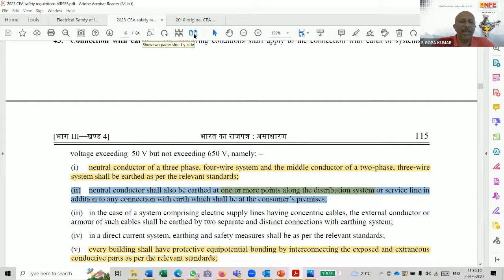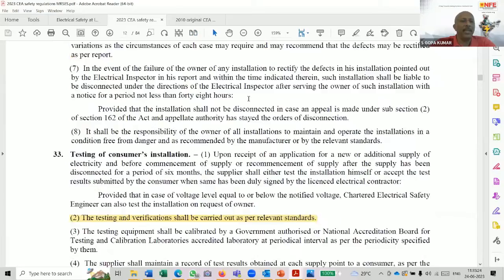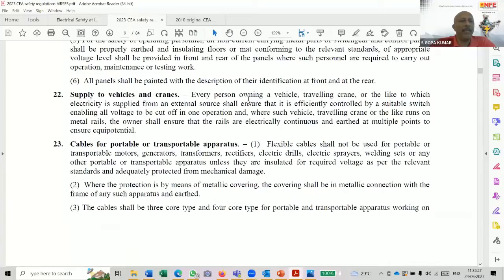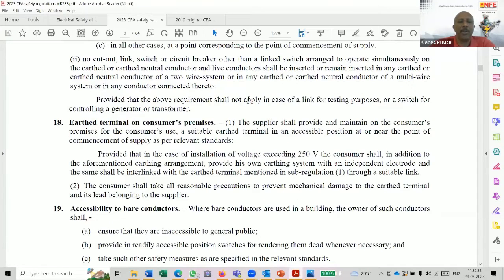So, sir, to conclude, in the majority of cases, the earth terminal under regulations 16, 17, 18 of the current regulations, especially the earth terminal in regulation 18, which was earlier regulation number 16, was not provided by the electricity supplier. Actually, I was in Kerala last week. There, the electricity supply company is giving a funny network. It looks like a TT, but on the distribution, the neutral conductor is earthed, whereas the earth terminal is not available in the consumer premises, because it looks like a TT at the consumer premises, and at the distribution it looks like a TNCS with PME.